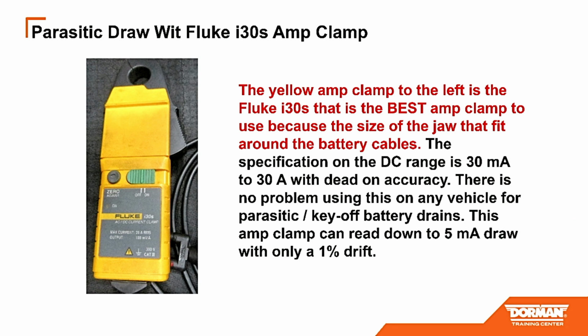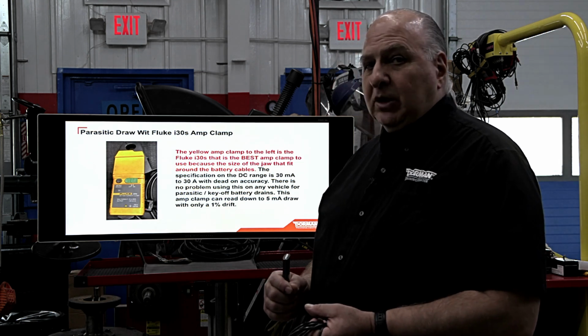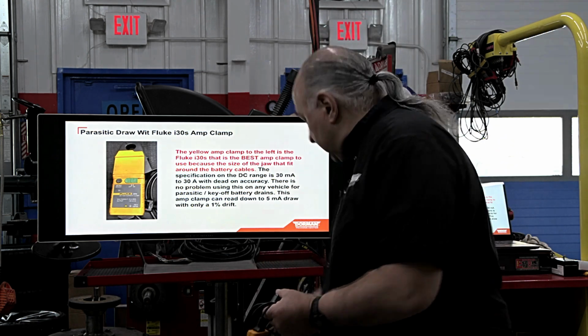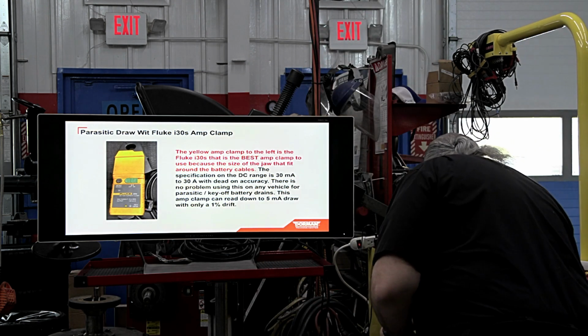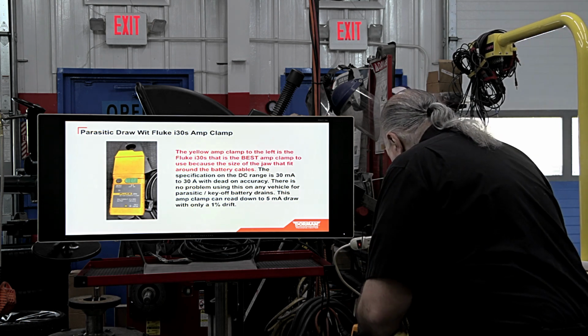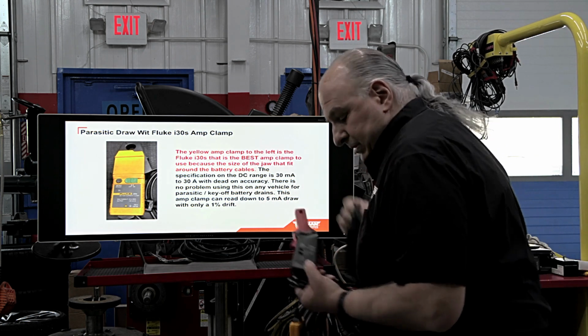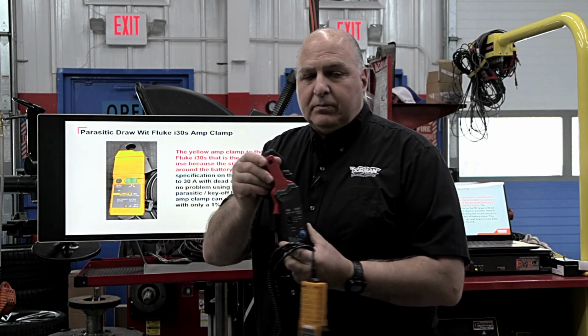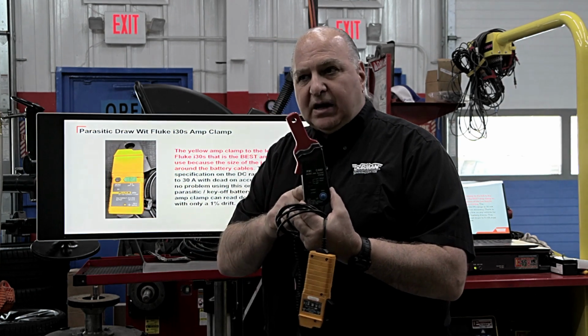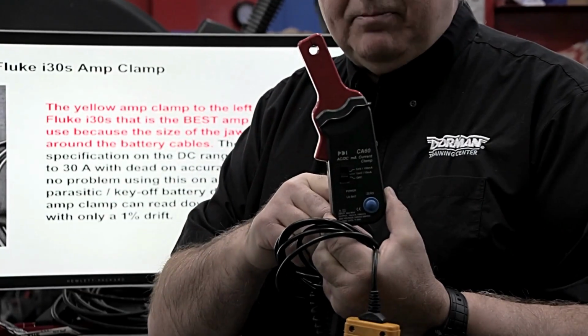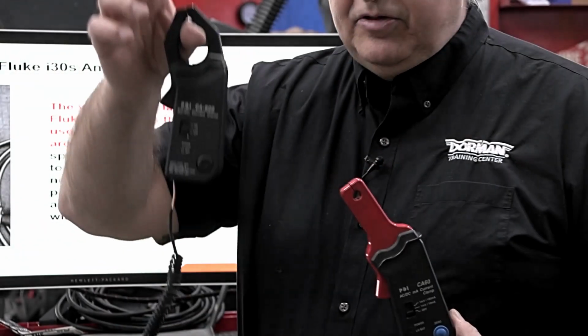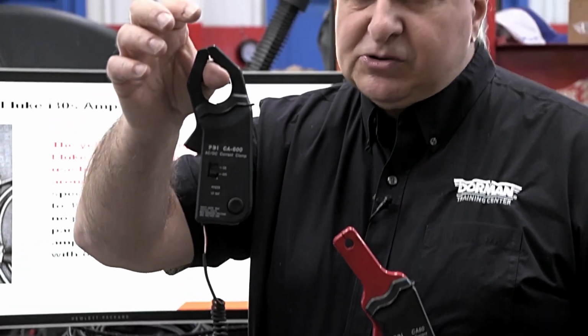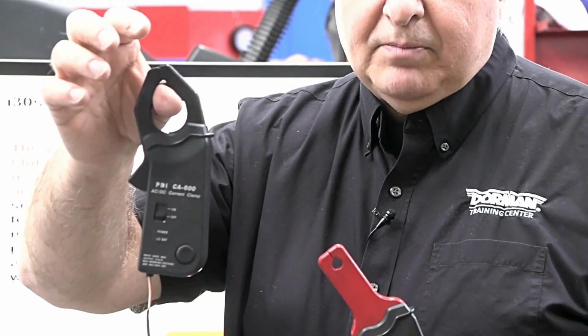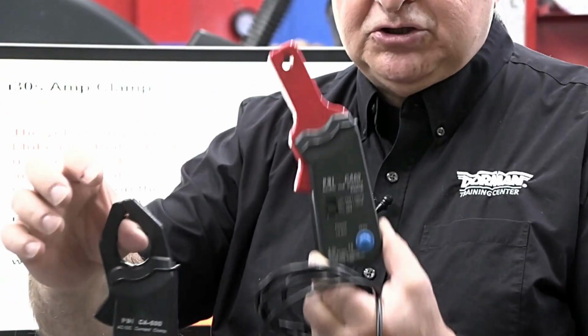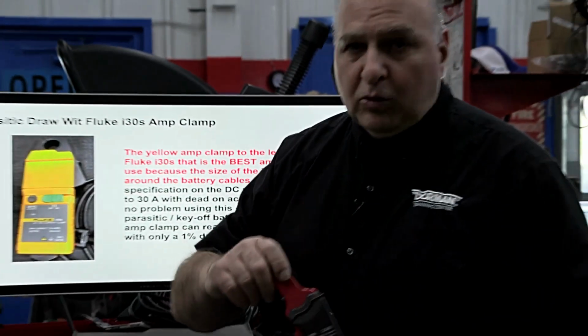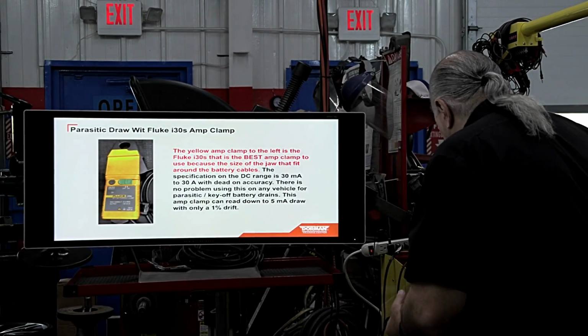So every amp clamp has a range. You may have a little PDI clamp - I'll show you a couple of different clamps here. You may have this clamp, for argument's sake, or this one. This is not going to work - number one, the jaw is not big enough, it won't be accurate enough. This one is for starter draw testing. This would not be good to use either because of the range. So all of these have ranges where they float or give good accuracy.